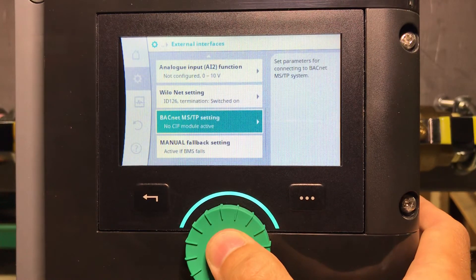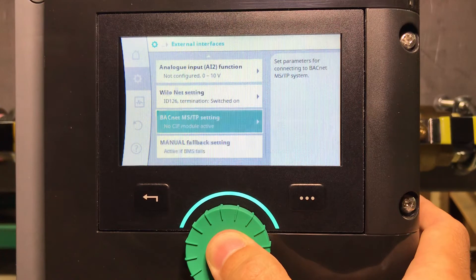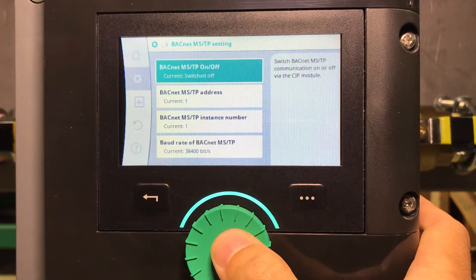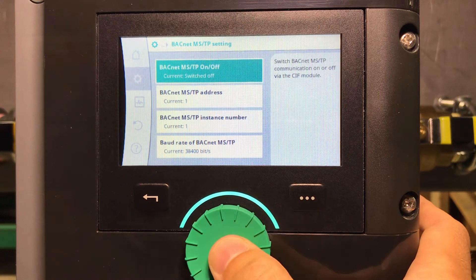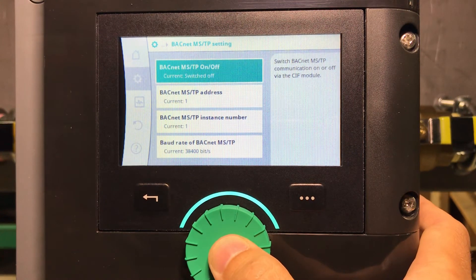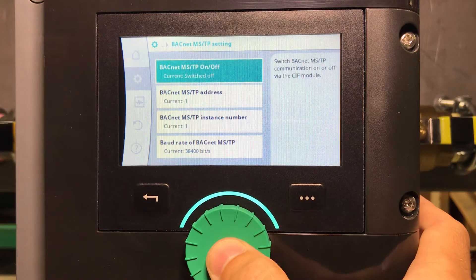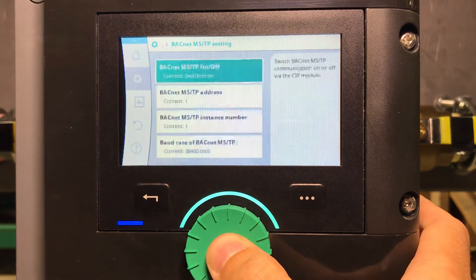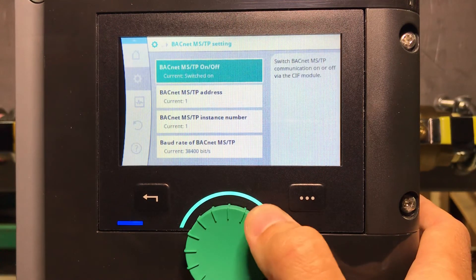In this case we want BACnet, so here you go — this is the BACnet MSTP settings. Even if you have the module installed, you can turn it off if you don't want to use BACnet. We will switch it on. The blue LED came on, which indicates that some sort of external interface is being used.